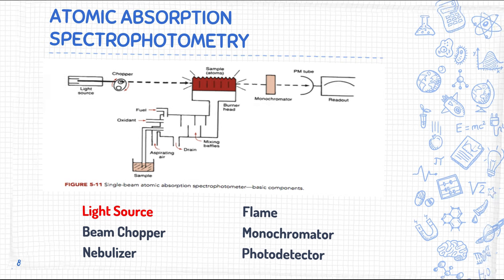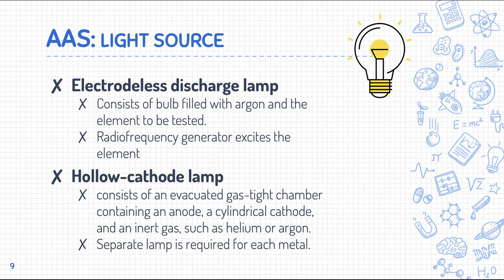The first component is the light source — the source of incident light. In AAS we have two types: the electrodeless discharge lamp and the hollow cathode lamp. The electrodeless discharge lamp consists of a bulb containing argon and the element to be tested, and uses a radio frequency generator to excite the element.